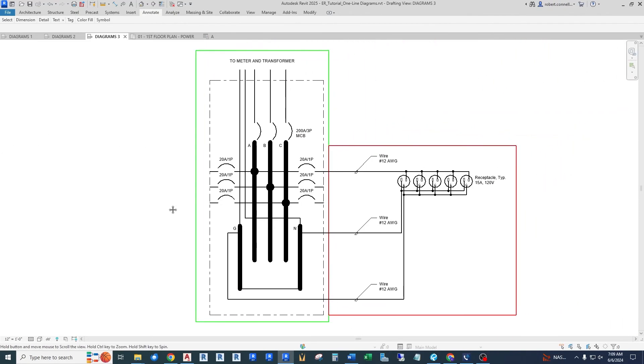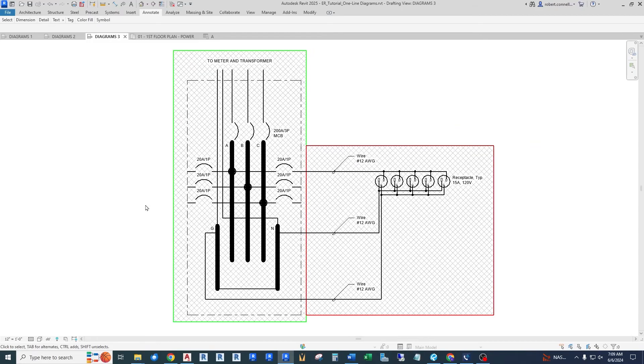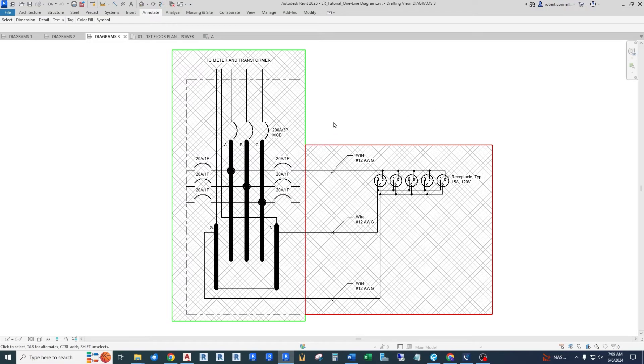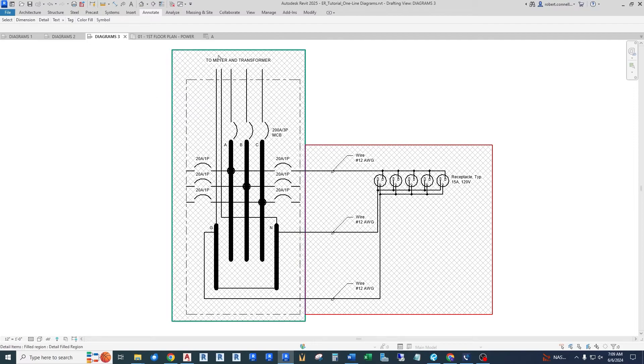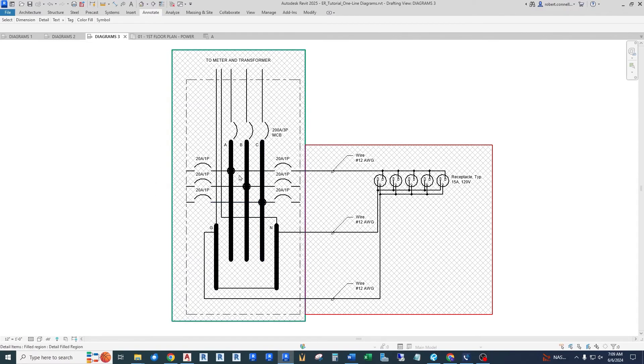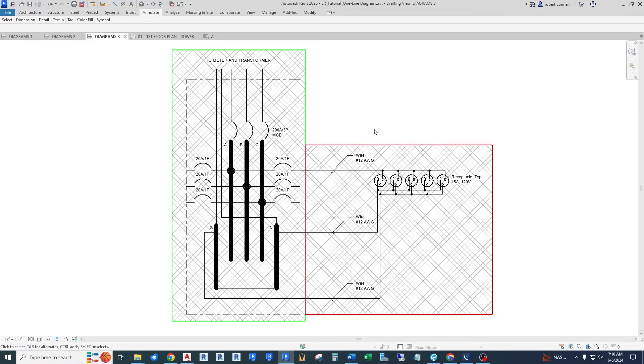So here's a diagram again. Same diagram, but I've color coded some pieces. So what we typically do in the electrical construction industry, we'll typically break this kind of system into two pieces. You have green, which is the distribution system. How do we distribute the electrical power throughout the facility or the campus or the city? The green stuff will be shown on a one line diagram. And then the load end of things, the hot, the neutral, the ground, and all of its connections will be shown on a floor plan view typically.